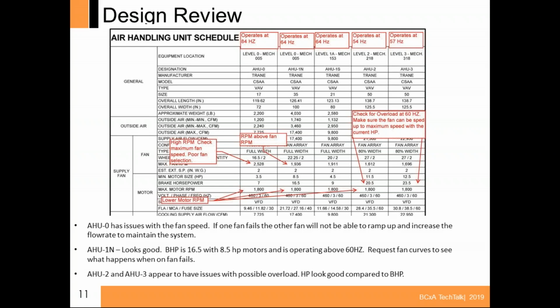And I said, you know, this is not acceptable, because if one fan fails, the other fan isn't going to do anything. And probably because the pressure's dropped so much, it's going to overload immediately. So you don't have any redundancy in this case at all. What's going to happen is that one motor fails, the pressure is going to drop, the other motor is going to spin out, it's going to go to the end of its curve, and that's it, particularly at 64 hertz. So I'd imagine that we've taken the drive and set the maximum hertz to 64.